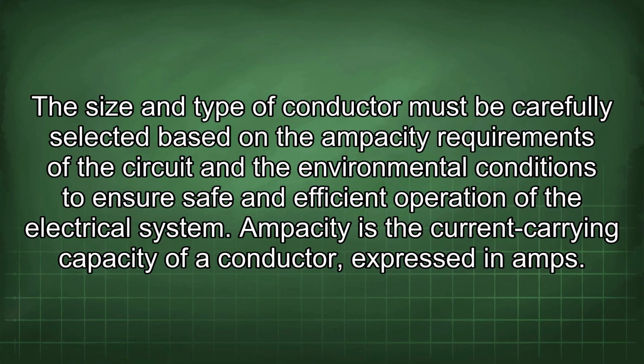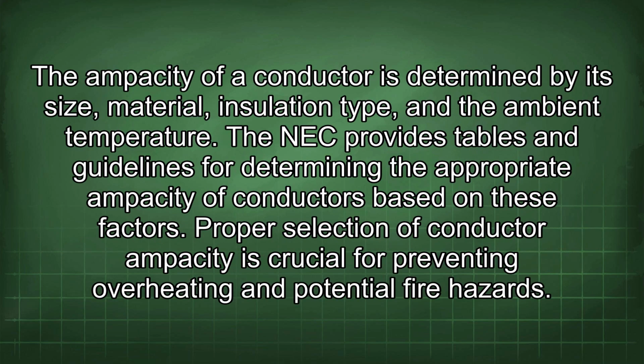Ampacity is the current carrying capacity of a conductor expressed in amps. The ampacity of a conductor is determined by its size, material, insulation type, and the ambient temperature. The NEC provides tables and guidelines for determining the appropriate ampacity of conductors based on these factors. Proper selection of conductor ampacity is crucial for preventing overheating and potential fire hazards.